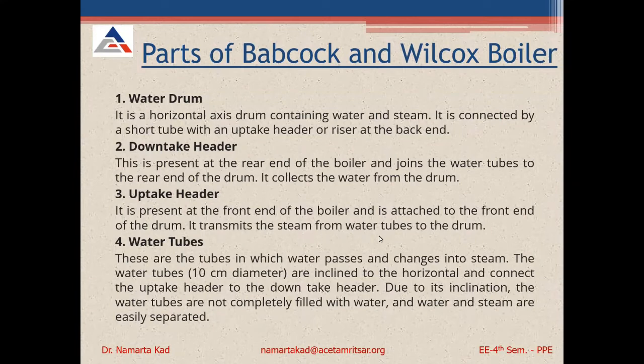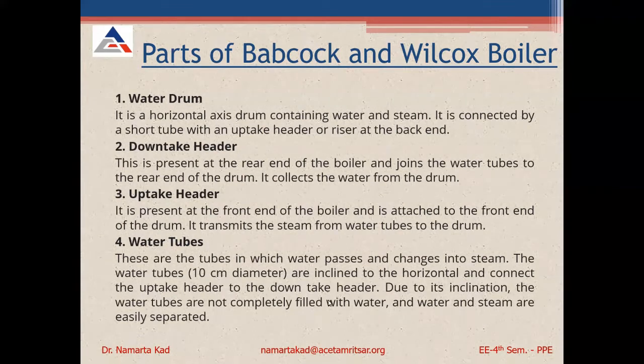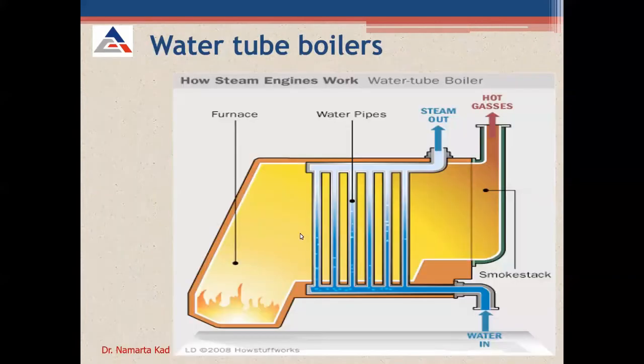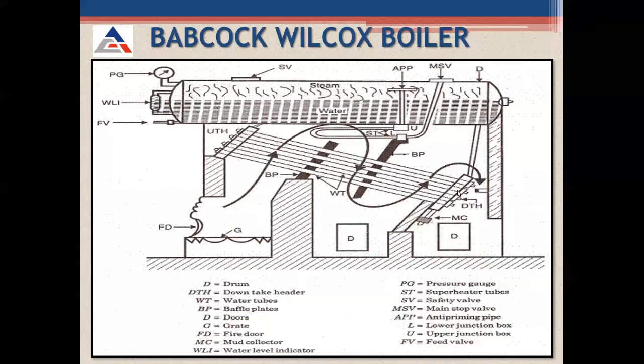The water tubes are the tubes in which water passes and changes into steam. These 10 cm diameter tubes are inclined to the horizontal and connect the uptake header to the downtake header. Due to their inclination, the tubes are not completely filled with water, so water and steam are easily separated. Water assembles near the downtake header portion, and as it heats, the steam moves toward the uptake header.